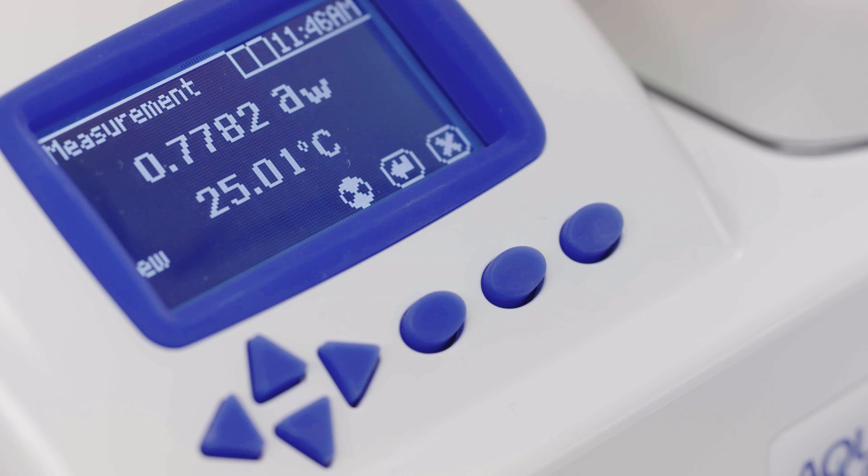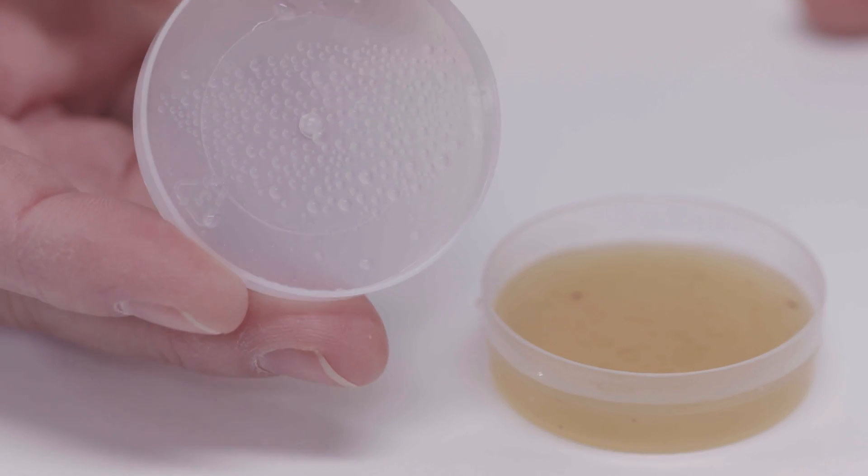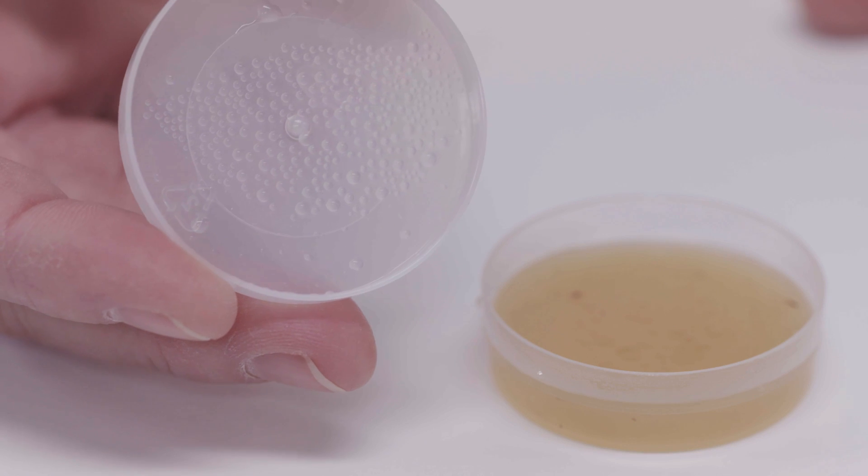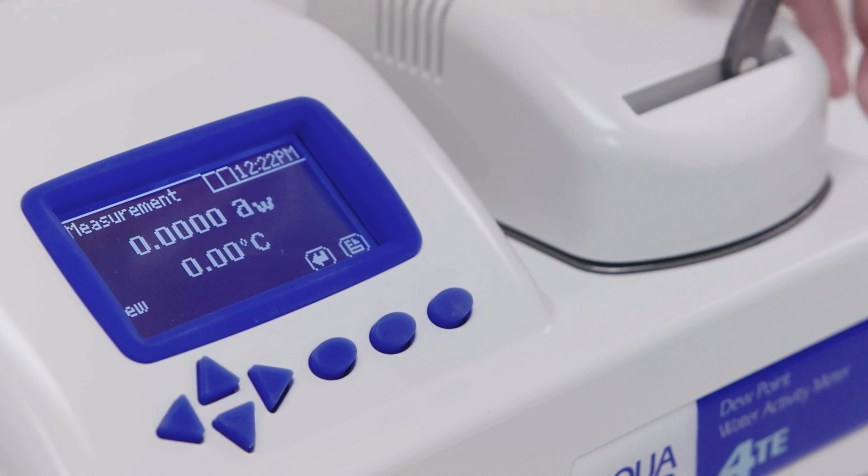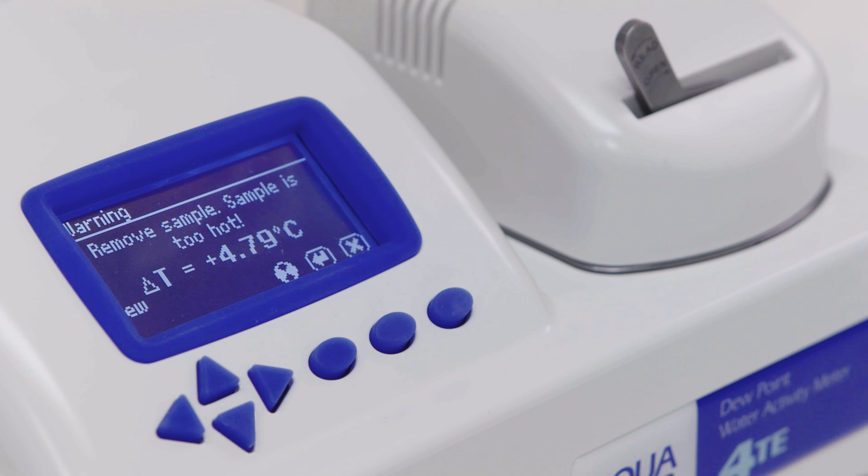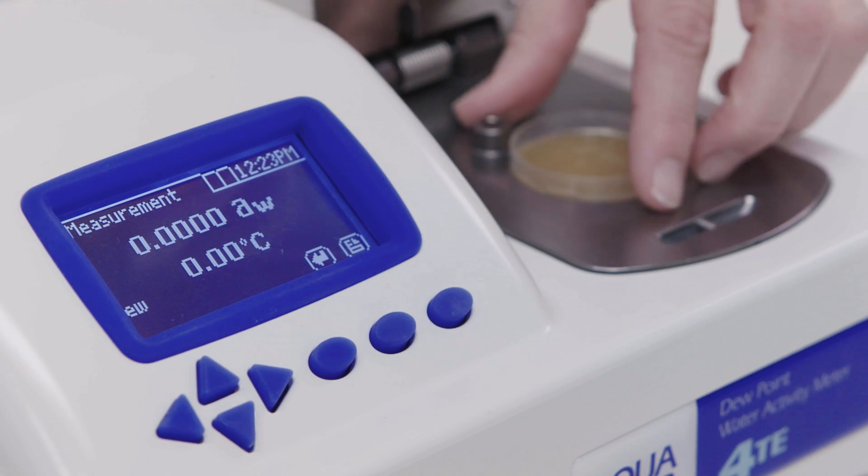Your sample temperature and block temperature need to be in the same general range before your reading can be taken. If it's too hot, water can condense on the inside of the sensor chamber. This ruins your water activity readings. If your sample is too hot or too cold, the instrument will ask you to take the sample out. If the temperature is only off by a few degrees, the instrument will wait as a sample comes to temperature.